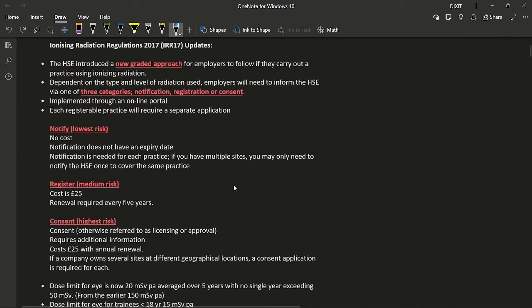Notification is for the lowest risk practices. It is a no-cost method, has no expiry date, and notification is needed for each practice. If you have multiple sites, you may only need to notify the HSE once to cover the same practice. Registration is for medium risk practices; the cost is £25 and renewal is required every five years.